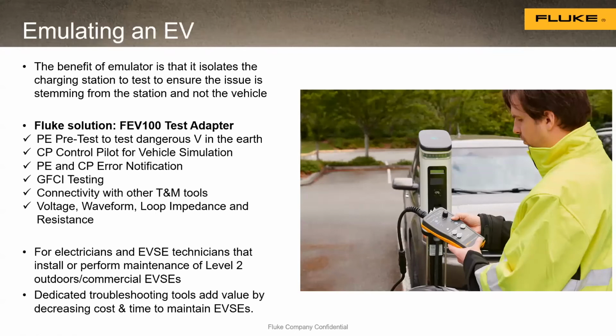We don't need the electric vehicle on scene anymore. All we need to do is plug in our adapter, and that allows us to run several tests on that level one and level two charging station. This lets us do a pre-check to make sure it was grounded correctly, and even control pilot simulation to confirm the communication piece is working correctly. Internally, these charging stations should have GFCI testing, ground fault testing, and maybe a CP error on that communication piece, so we can simulate an error and see what the charging station does.